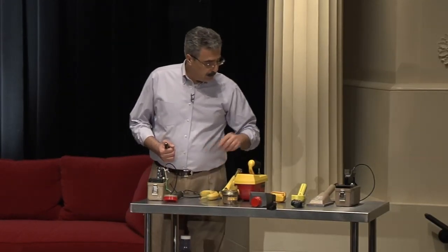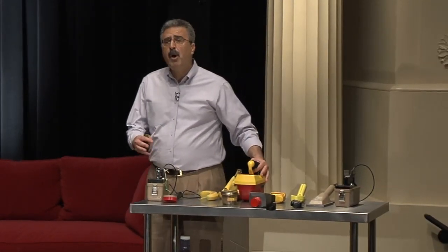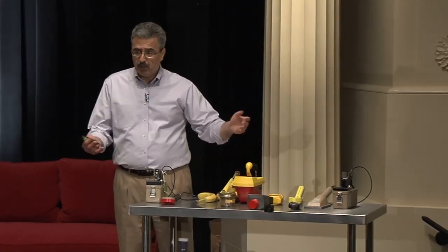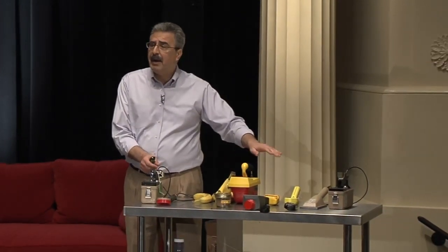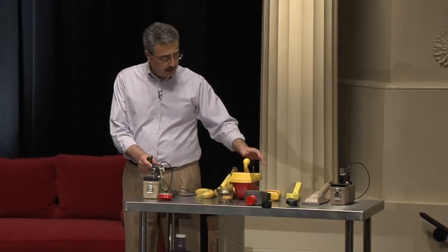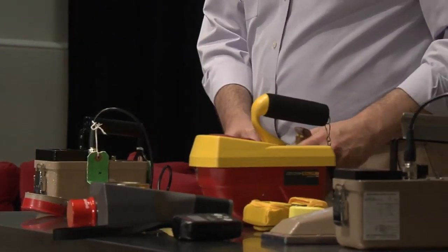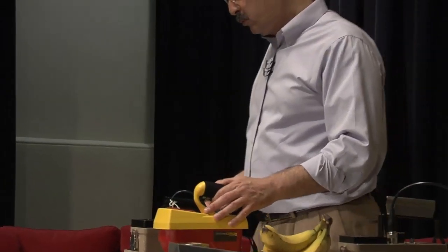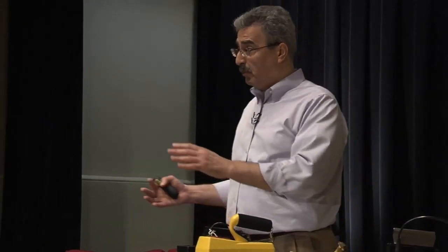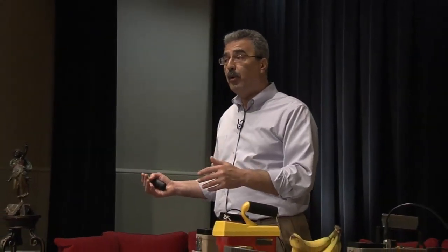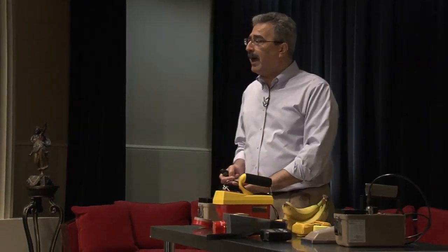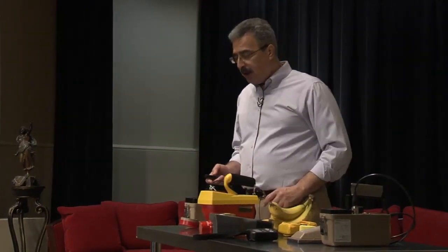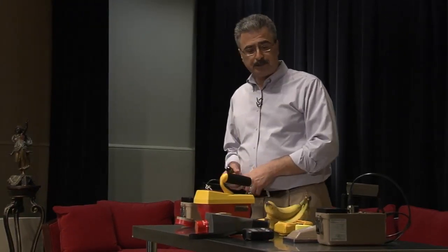Another instrument is the ionization chamber, and there are different models of this. The ones I have here are just one particular model, but there are different brands and models of all of these instruments. An ionization chamber is a very good instrument to measure ambient radiation levels. Geiger counters would give us an idea about whether the ambient radiation levels are high or low, and give us some measure. But to make a more accurate measurement, we would need to use an ionization chamber.